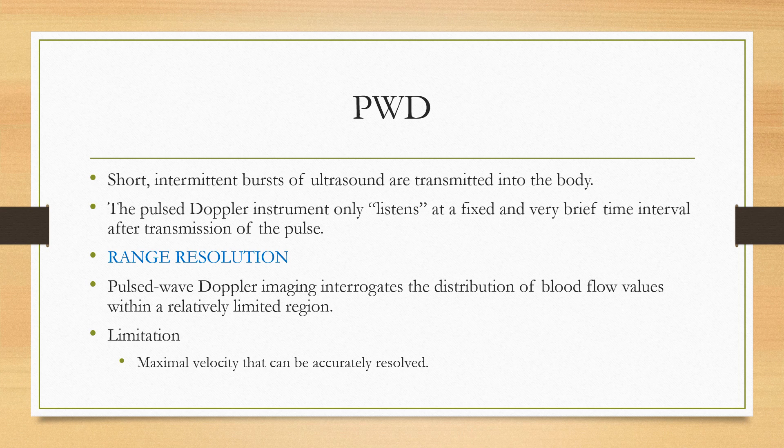The main limitation of Pulse Wave Doppler is that there is a maximum velocity beyond which it cannot be accurately resolved. To understand that, we need to understand Pulse Repetition Frequency, aliasing, and the Nyquist Limit.